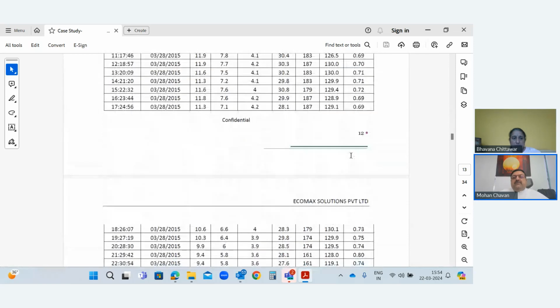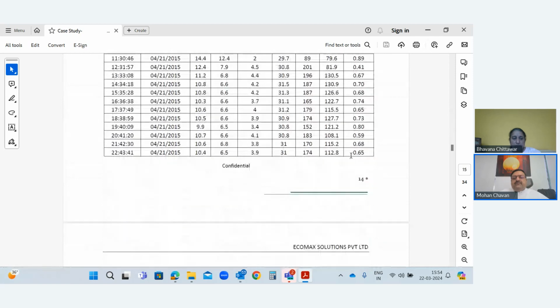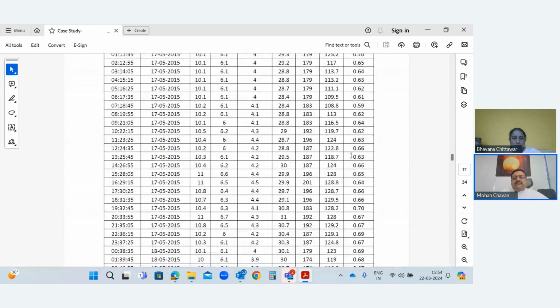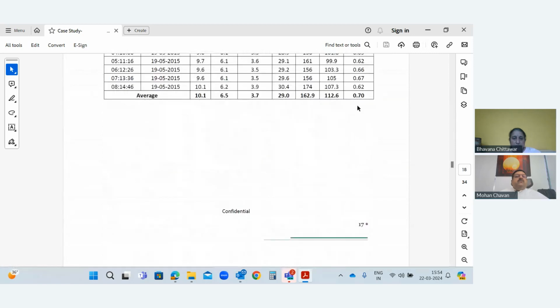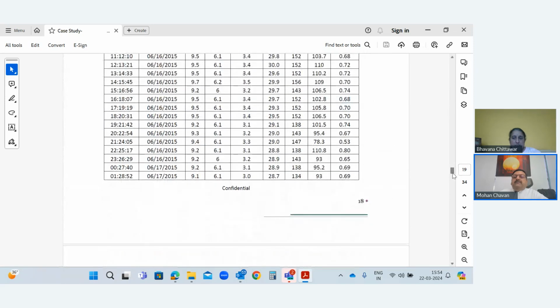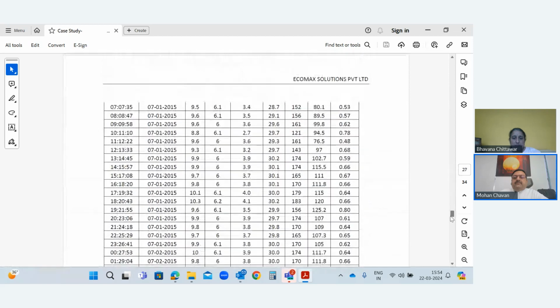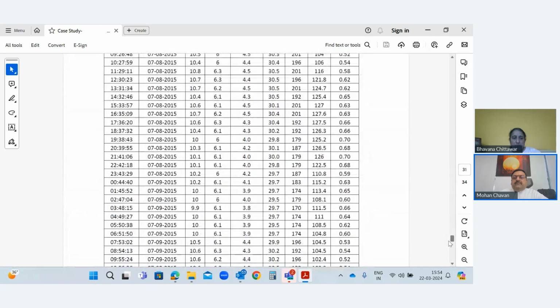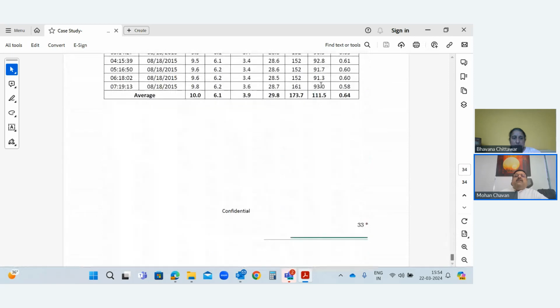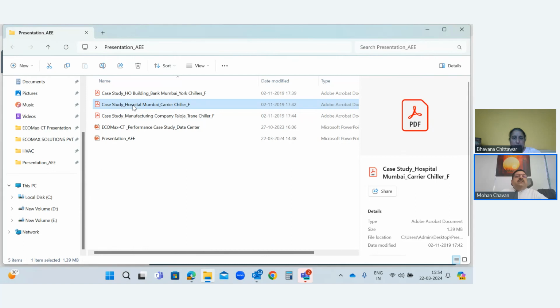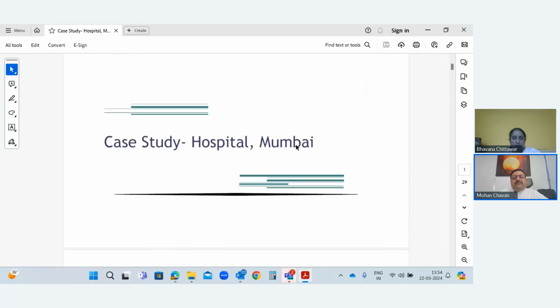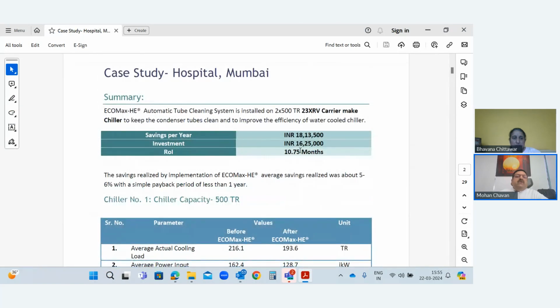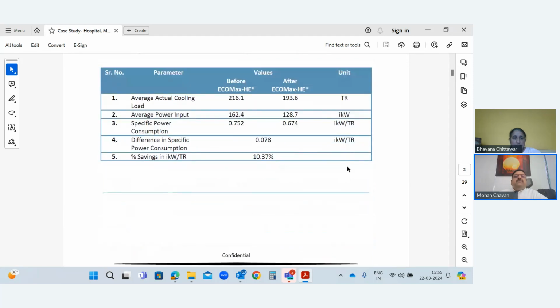So on an average, if you see below, this was before, 0.7 was the IKW per TR before. After was 0.64. Okay, this is the log data. And there is one case study for the hospital also, wherein again the payback was less than 1 year for this hospital for 2 into 500 TR chillers, around 10% improvement.